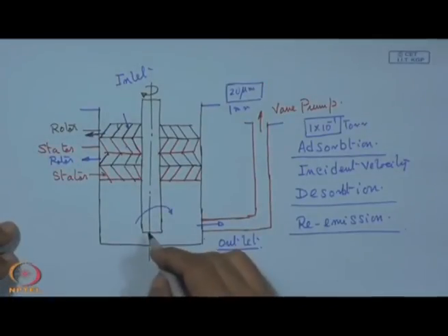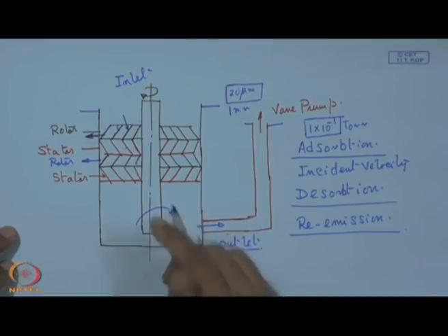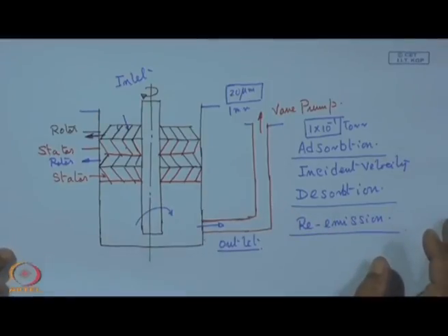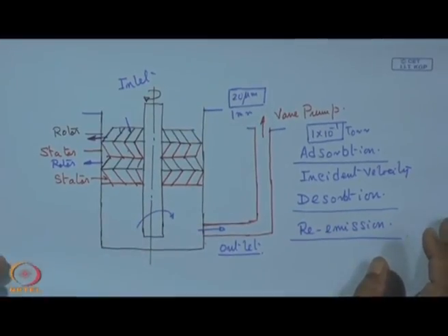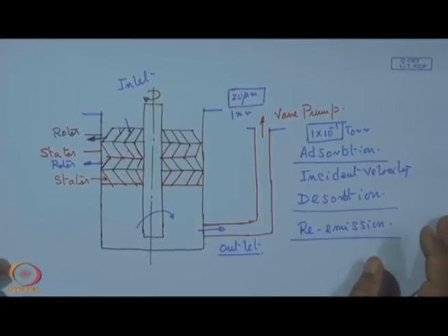Here the only issue is the rotational speed, and these pumps are put with a vertical shaft, a vertical axis, because of the orientation of the chamber, and in that case the alignment of any shaft with two end bearing supports in the vertical position, considering any mechanical assembly, is one of the greatest challenging tasks in the construction and fabrication of this pump.